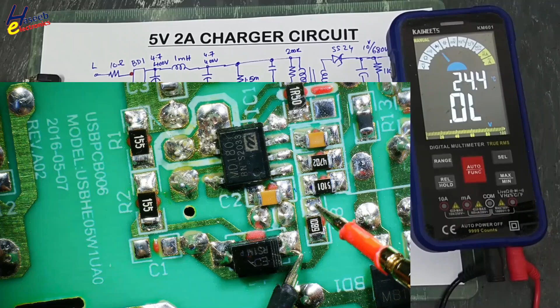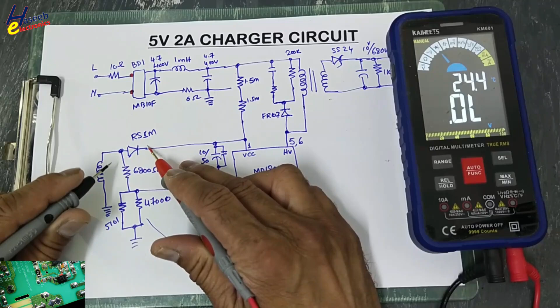Now from the auxiliary winding's this end to this point, open circuit, one diode. This time I tested this winding with this rectifier. If this rectifier is short circuit, it will give an indication in both directions.